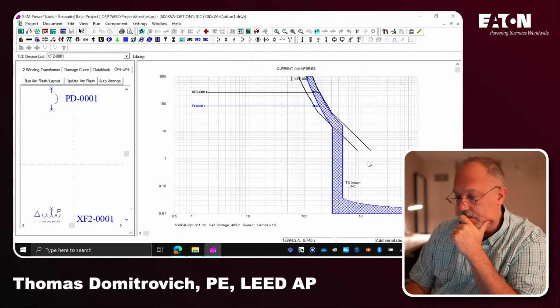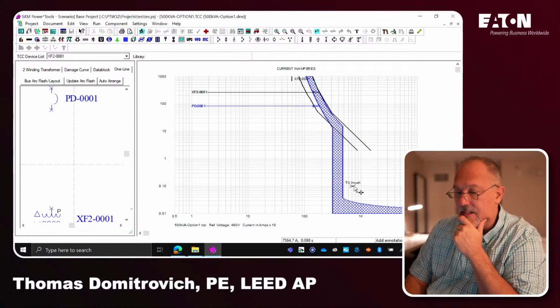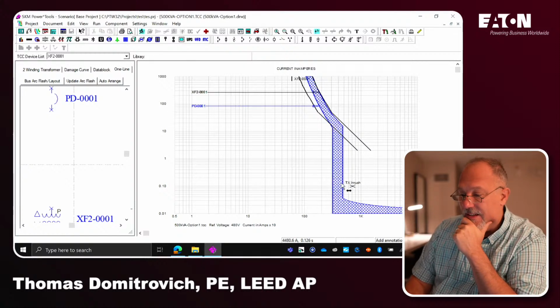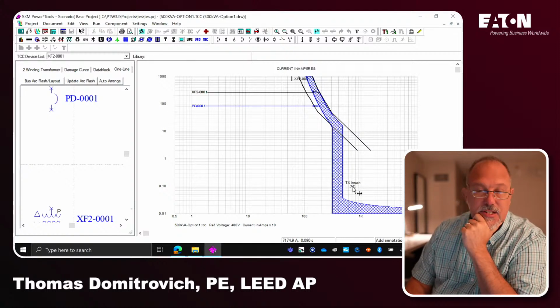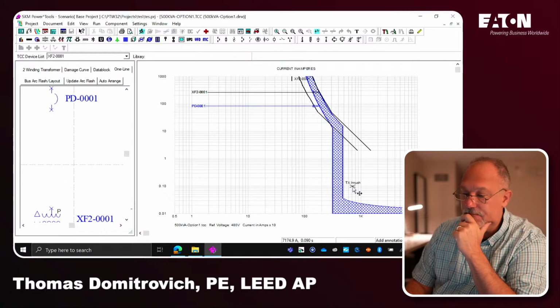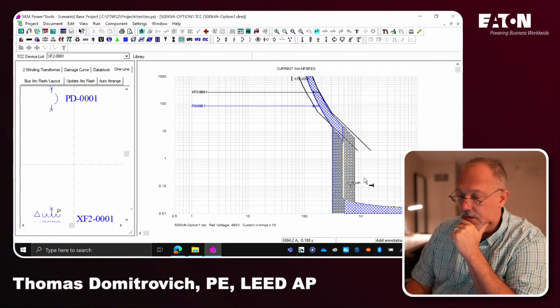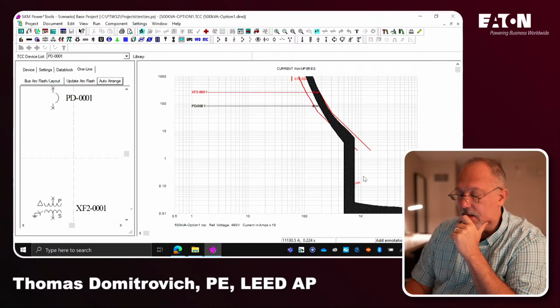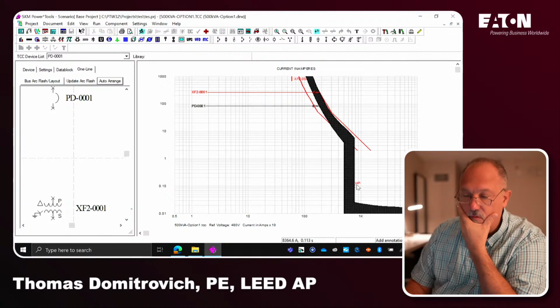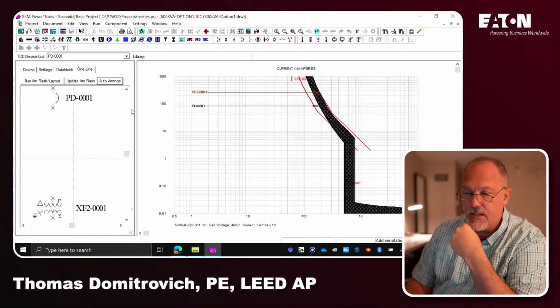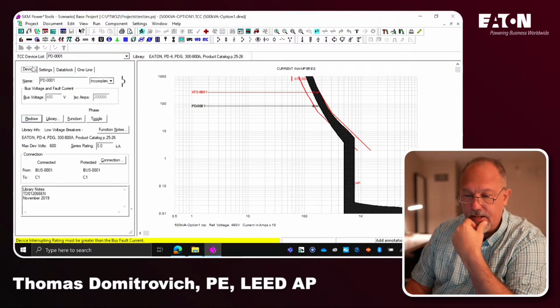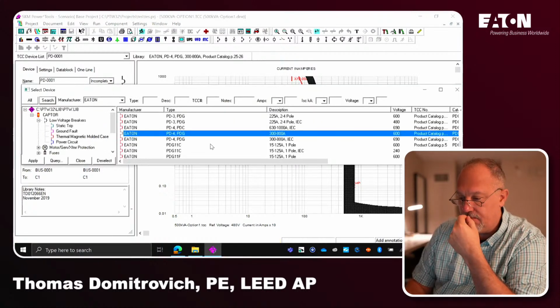So now you've got your transformer inrush. Now this is the primary breaker. If my inrush current is to the right of the instantaneous, it's going to trip. This breaker does not look wunderbar. I'm going to try to change this breaker. Let's go back to device, library.